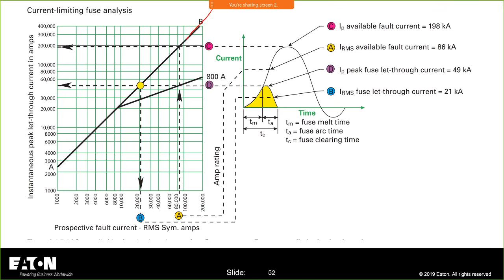The AB line is basically when there's no current limitation in the picture. This point right here is when it goes into the current limiting region. Any currents below this number will not be in the current limiting region of this fuse. And if I wanted to translate that data point, if I thought about a time current characteristic curve and say my fuse curve looked like this, the point right here at 0.01 seconds is going to be right in there. That's the point at which it starts to become current limiting. This portion of that curve is basically right in here. And remember what you're looking at.